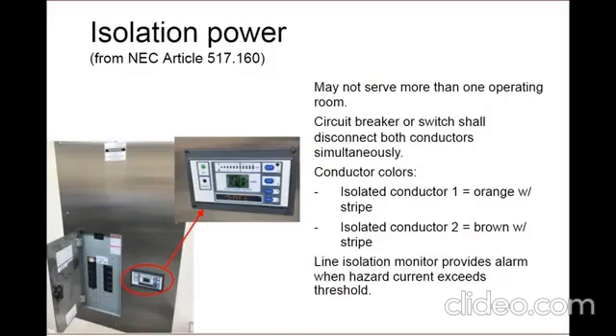An isolated power system is an ungrounded distribution system with a monitor to alarm when leakage current from a ground fault occurs. The circuits remain energized during a line-to-ground fault, but also keep the patient from experiencing electric shock from the leakage current. NEC 517.160 contains provisions for isolated power system installations. The isolation transformer may only serve one operating room. There are a couple of exceptions for induction rooms that may serve more than one OR, and also equipment operating at higher voltages, above 150 volts.